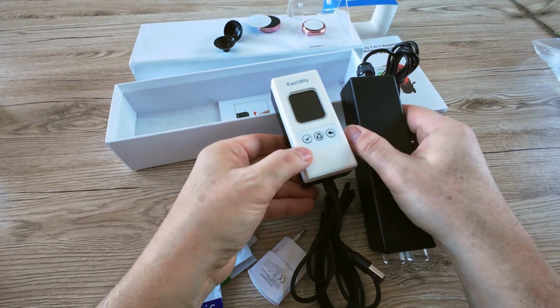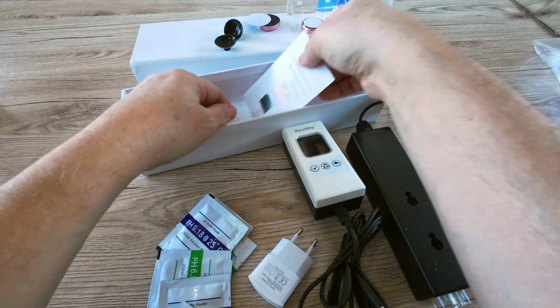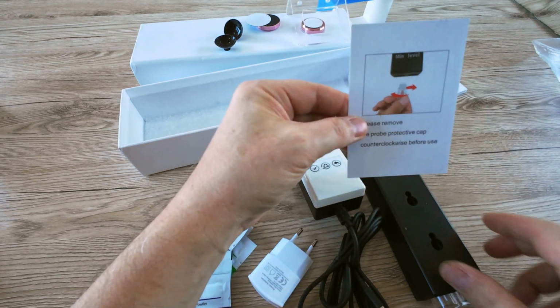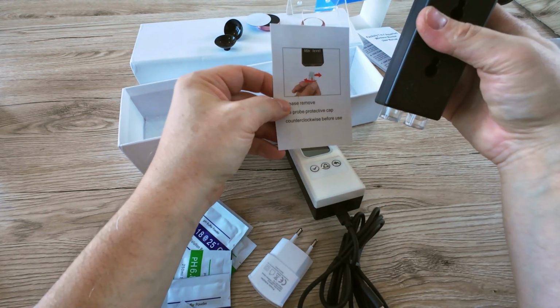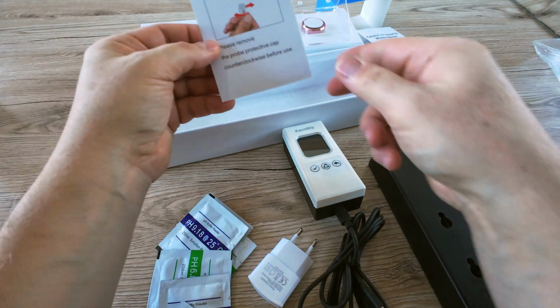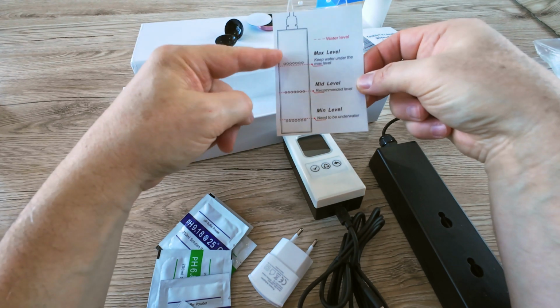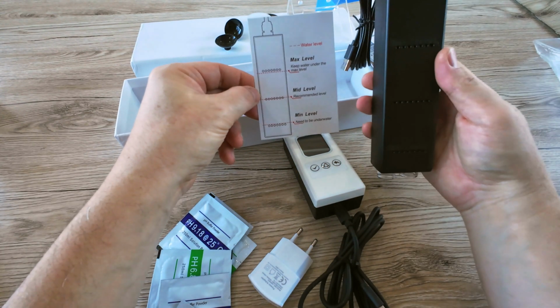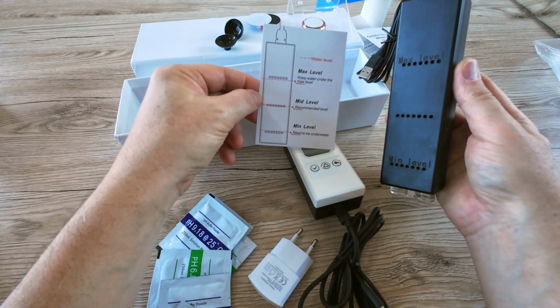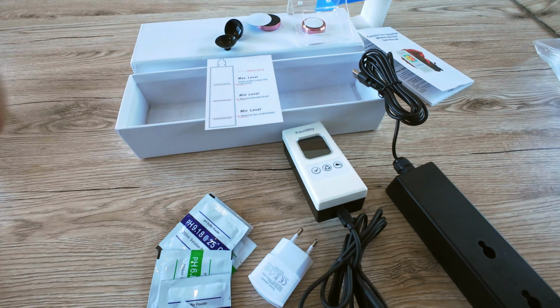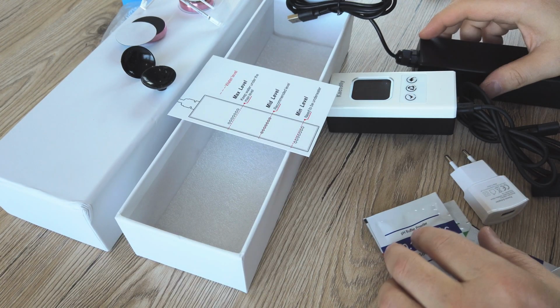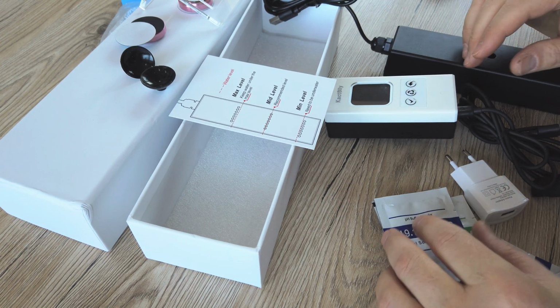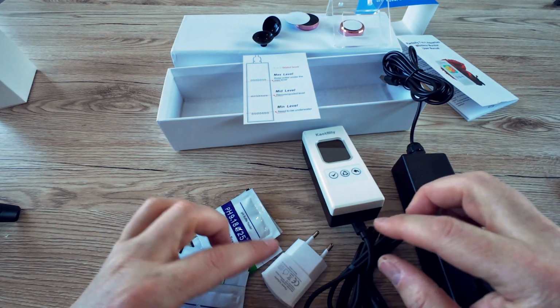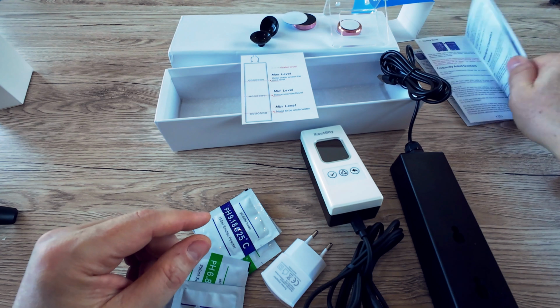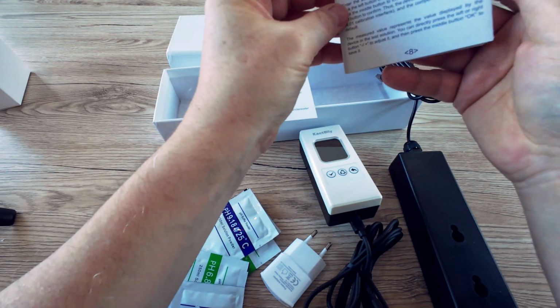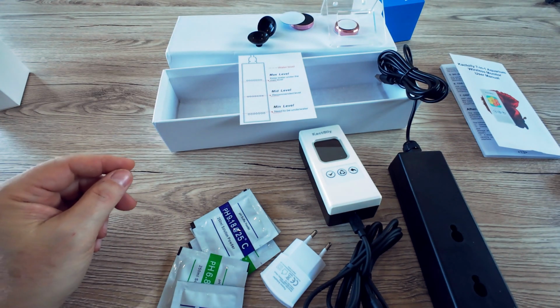Okay, here. What else do we have here? This is a warning that you need to remove those cups from the probes. And here are the markings for the levels between which the probe is to be submerged. There are holes on the probe at each level. Well, that should be all we have in the package. It looks interesting and very simple. We will try to wire it all up, see how it fits into the sump, and set up the main parameters like temperature, pH and specific gravity if we need to.